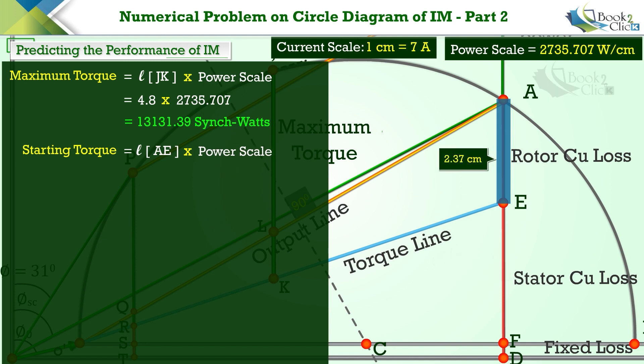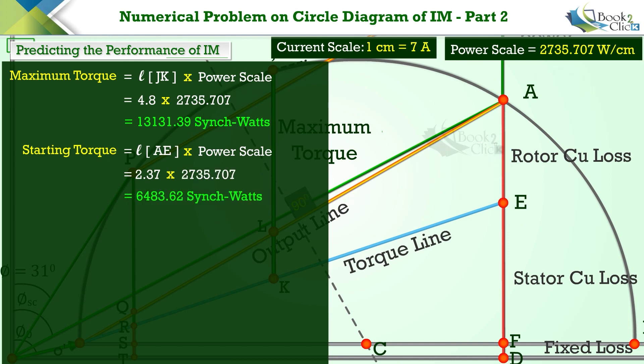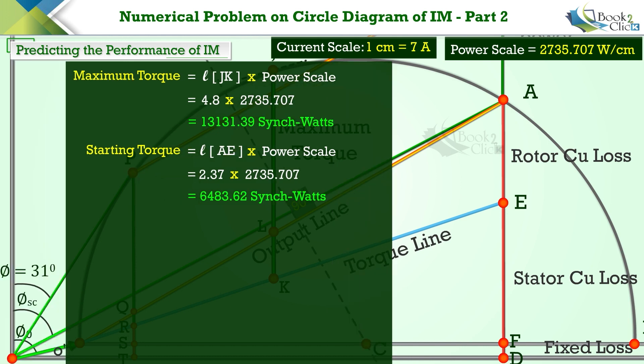To determine the starting torque of this motor, multiply the length of line AE by the power scale value. The length of line AE is 2.37 centimeters, and hence the starting torque is 6,483.62 synchronous watts.